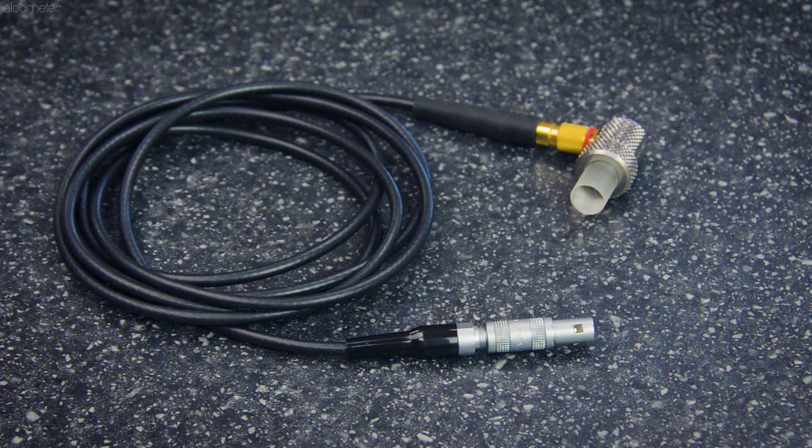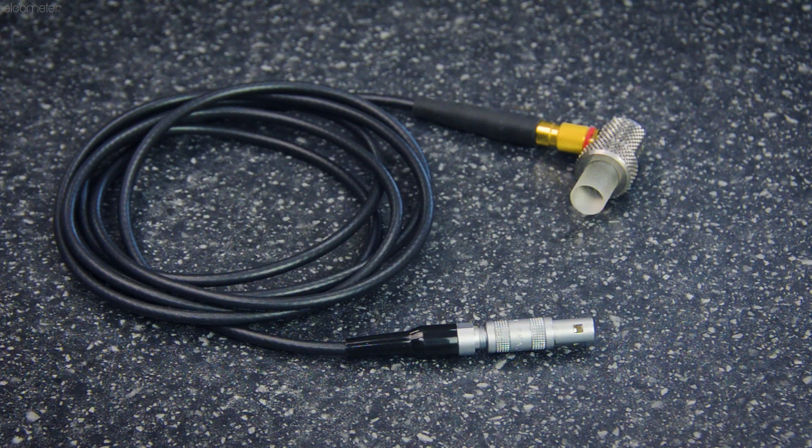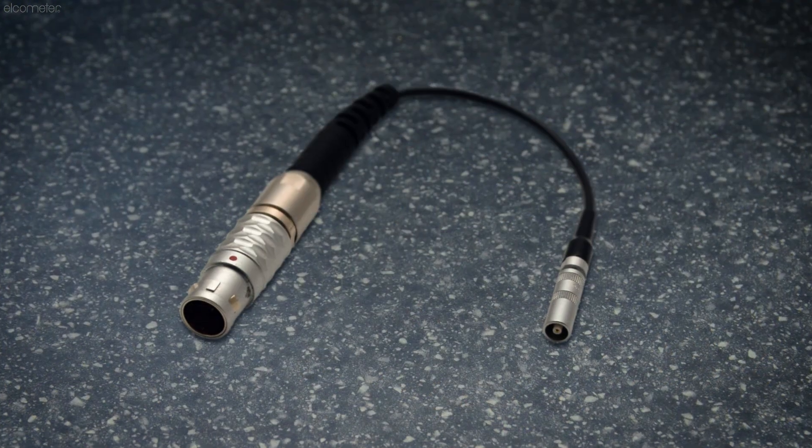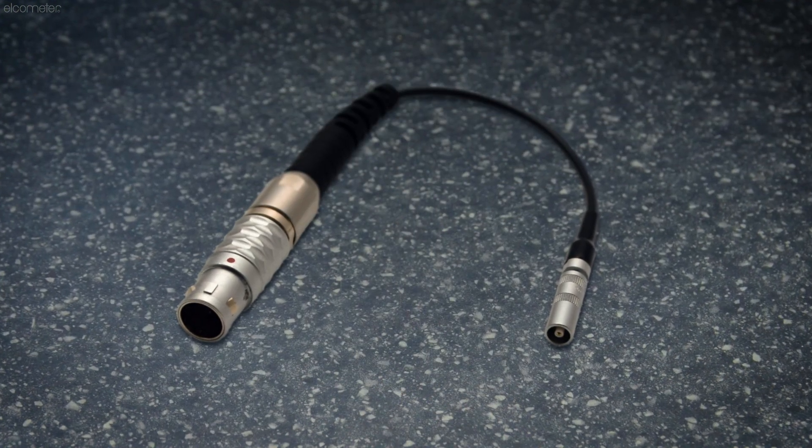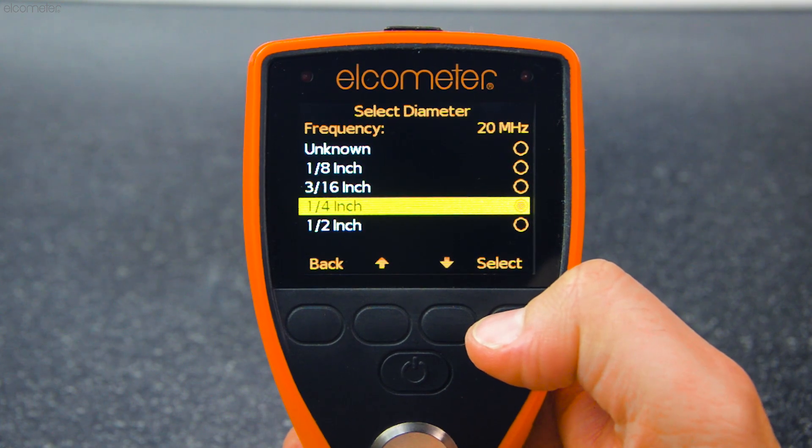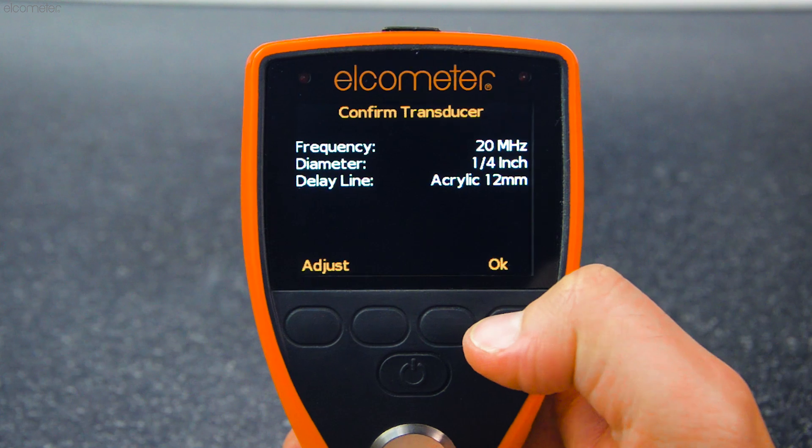If you already have a range of transducers you wish to use which have LEMO connectors, they can be connected to the Elcometer PTGs using a single element transducer adapter. You simply tell the gauge what transducer you're using, as well as the delay line.